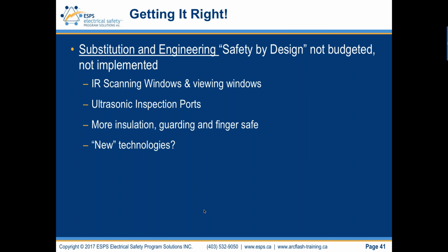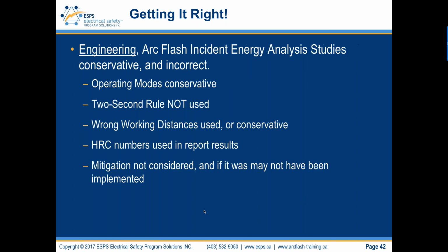And new technologies are evolving around us all the time. New technologies in the equipment, new technologies in the PPE, and there's been some new products brought out from, you know, major manufacturers of test instruments that help. Probe extenders. Right, extending the probe, hands are further out of the box, the worker can see their work better, their hands are still going to require rubber insulating gloves, leather protectors due to inadvertent movement risk, but probe extenders, simple, low cost, and drives down both arcing fault probability and shock risk exposure.